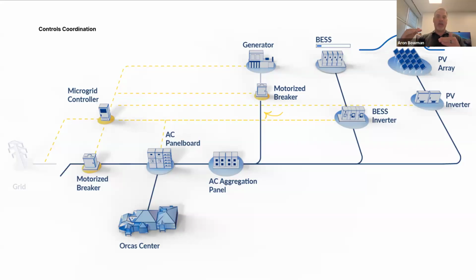The generator's running the cleanest, the generator's the happiest. Then we're charging or discharging those batteries, which can react in milliseconds to handle load shifts and changes. Once the batteries reach a certain state of charge, we'll shut the generator off and just have the batteries operate.